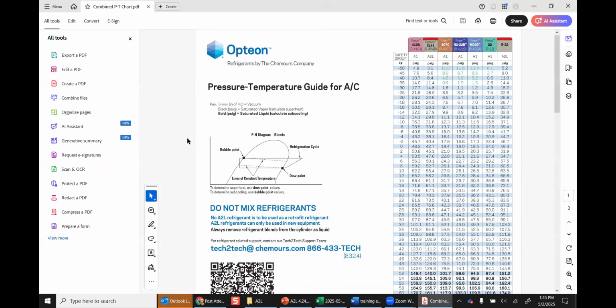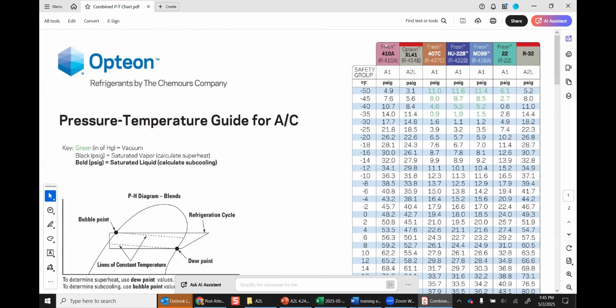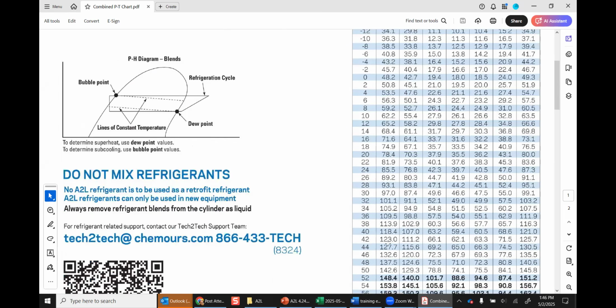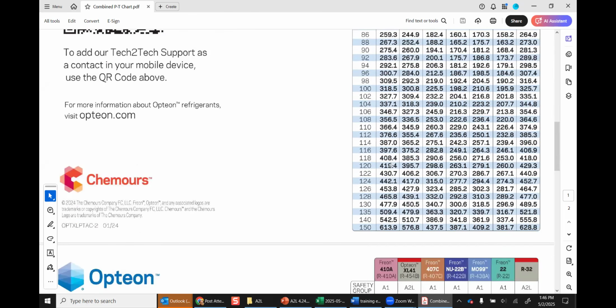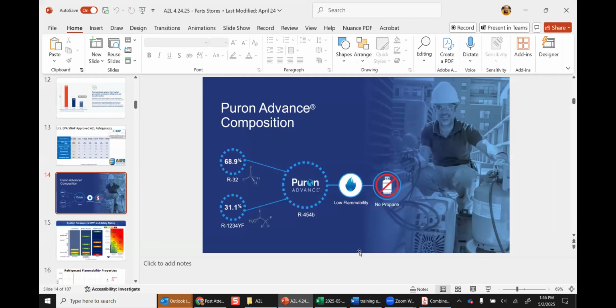Let me see if I can open up a PT chart real quick. So this chart, this one's nice because it has all these refrigerants in there at the same time. This is 410A. This right here is 454B. Oops, I clicked on it. And this is R32 on the far right-hand side. So if we look at an evaporator at, say, 40 degrees, R410A would be 118 for pressure. R454B is slightly less at 107, and R32 is slightly more at 121. But general same ballpark. Look at the outdoor side of the equation, let's say 120 degrees. I'm at 419 for 410A, 396 for 454B, and 429 for R32. So same general ballpark, but in fact, different.